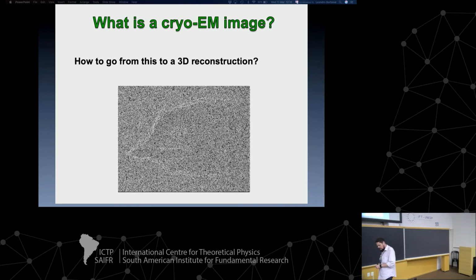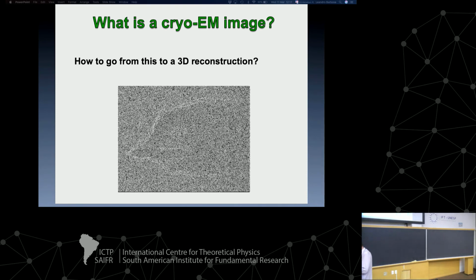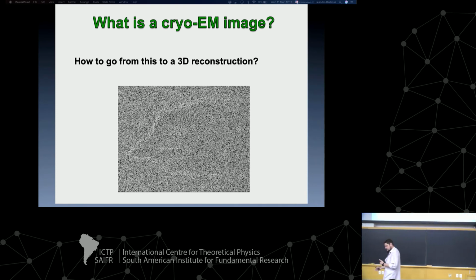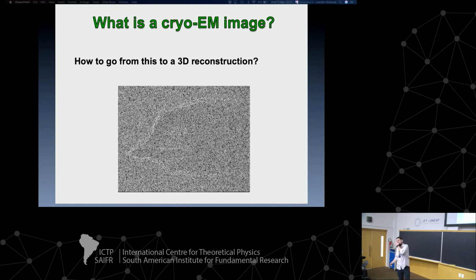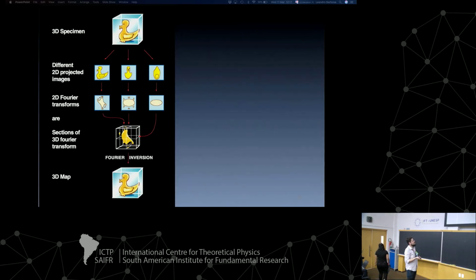This is because, in order to better see this stuff, you must get out of the focus of your lens, of your beam, and when you go out of the focus, you lose resolution. The nearer you are to the focus, the higher your resolution. However, if you are exactly at the focus, you cannot see anything because you don't have any information from your electron waves. So this is why we have several different kinds of software and algorithms being used to try to reconstruct the samples using this kind of information.